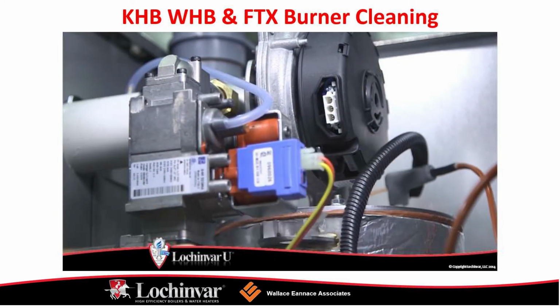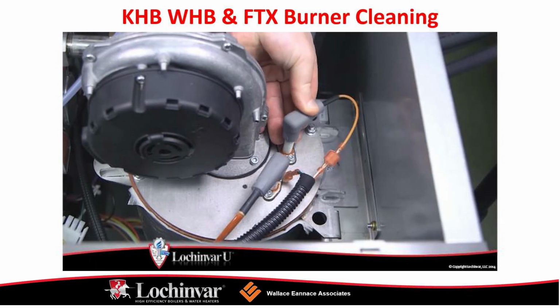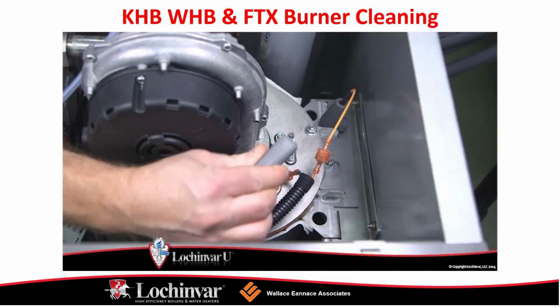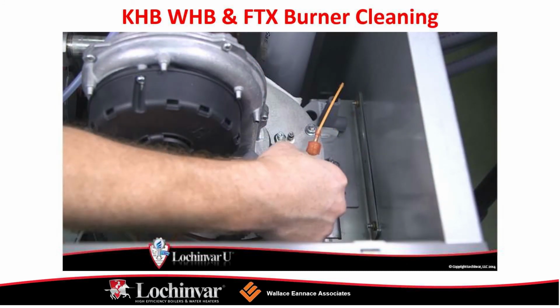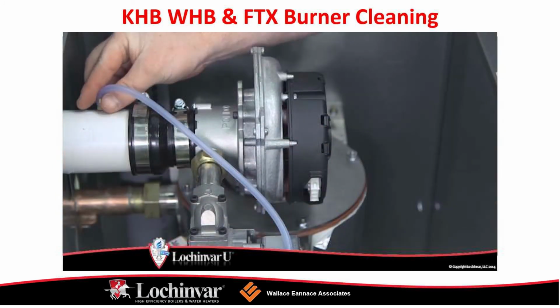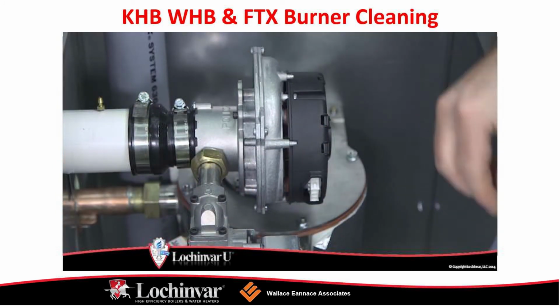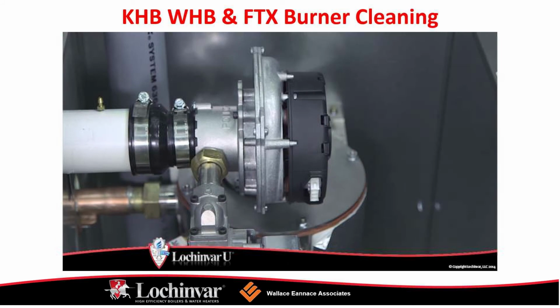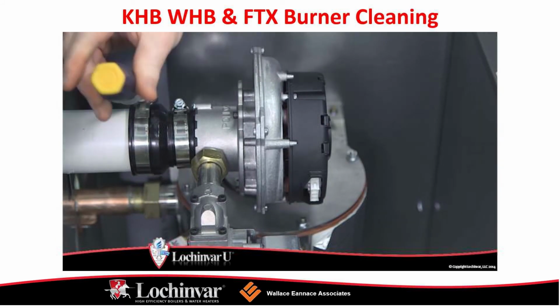Burner cleaning. Burner removal and cleaning. Locate the on-off switch on the side of the unit. Turn the switch to the off position. Turn off the main gas supply to the unit at the external main manual gas valve.